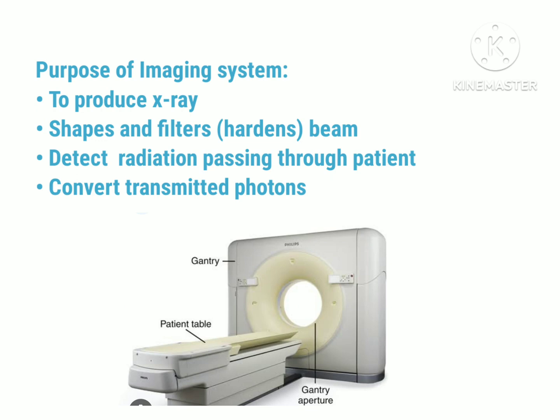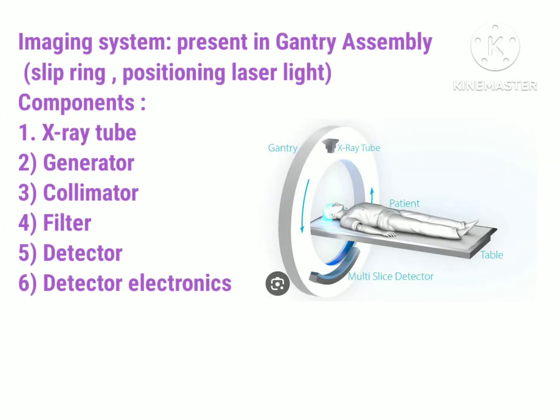Now let's discuss the imaging system. The imaging system helps to produce x-rays, it shapes and filters the x-ray beam, it detects or measures the radiations being passed through the patient, and it converts the transmitted photons. The imaging system is present in the gantry assembly, and the components present in the gantry assembly are: the x-ray tube, generator, collimator, filter, detector, and the detector electronics known as DAS.